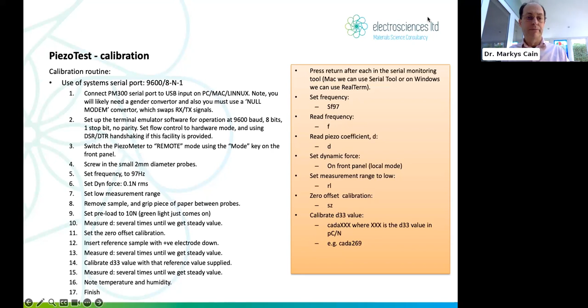Okay, so, oops. So, calibration issues. Now, calibration. What do we do? How do we calibrate the machine? What's the best way of calibrating the machine? Lithium niobate and quartz are two materials which have a very well-defined piezoelectric coefficient. They're very well, theoretically defined, actually, these two material systems. They're single crystal, these materials. They are piezoelectric. Lithium niobate is also ferroelectric. Quartz is not, but it is piezoelectric. And the values of the piezo coefficient are quite low.